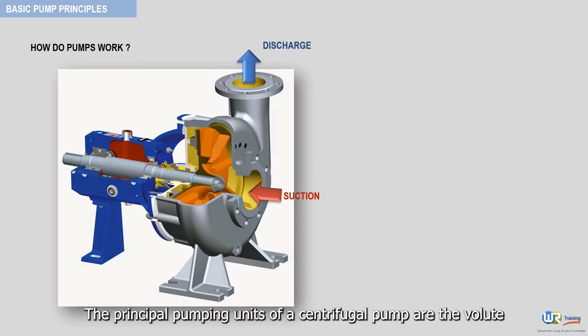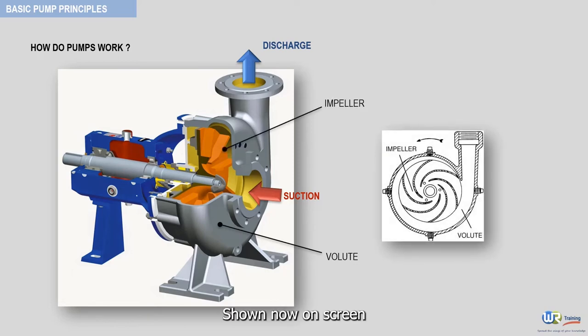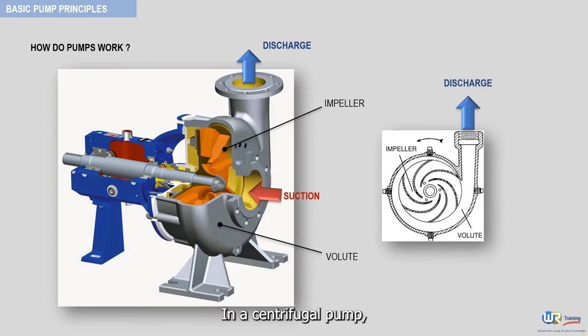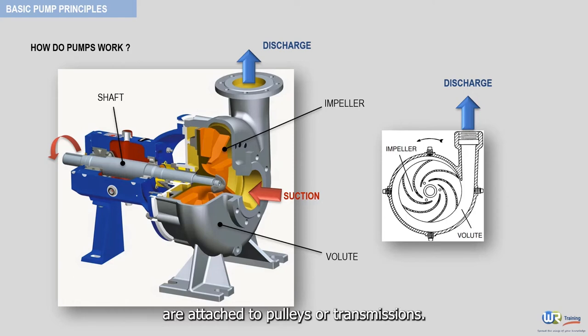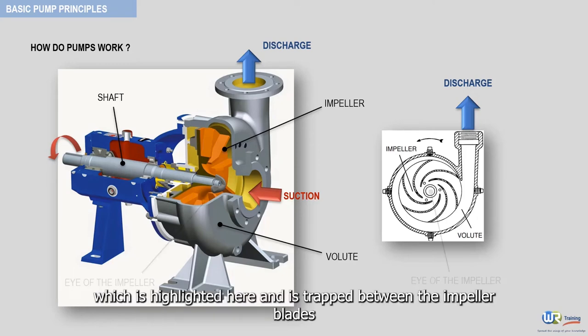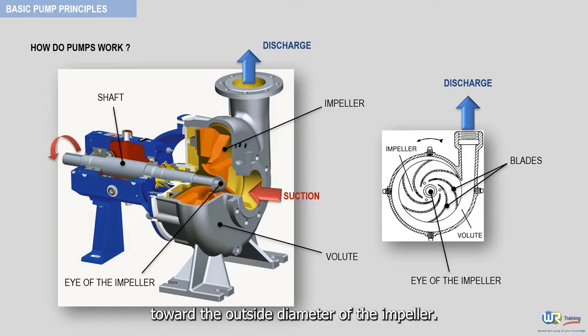The principal pumping units of a centrifugal pump are the volute and the impeller. Shown now on screen is the front view of the volute-impeller assembly with the discharge nozzle. In a centrifugal pump, the impeller is attached to a shaft. The shaft spins and is powered by an electric motor or driver — we use the term driver because some centrifugal pumps are attached to pulleys or transmissions. The fluid enters into the eye of the impeller, highlighted here, and is trapped between the impeller blades, which impart speed to it as the liquid passes from the impeller eye toward the outside diameter of the impeller.